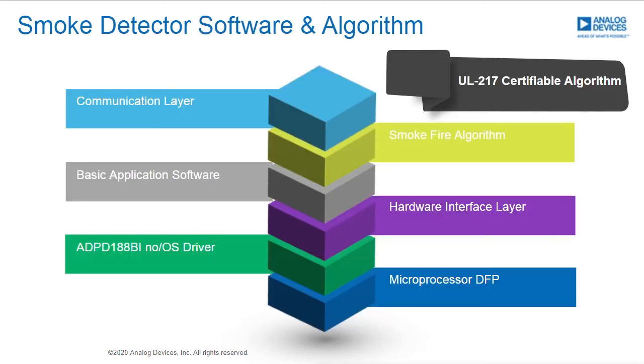But the key part of the solution will be a software algorithm that will be developed using test data. And currently, we're gathering many hundreds of smoke and fire test sample data sets from the UL 217 test configurations. This algorithm will focus on UL 217 alarming certification, so those key areas of smoke versus non-smoke, which translate to the real alarm versus the nuisance alarm. And it's going to be designed using various layers and protocols as shown here, so that it can be simply stitched into any design with any microprocessor system.